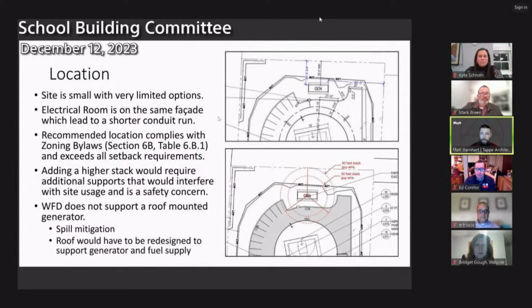We worked with our acoustical consultant to make sure that the control of noise to the neighboring properties was met for the DEP requirements. This location was also chosen due to its proximity to the electrical room, which is on the same facade. We looked at other options around the building as well, but moving it to the other side of the building led to a much longer conduit run, and we also did not want the conduit runs going underneath the building. The recommended location complies with all the zoning bylaws, section 6B, table 6B.1, and exceeds all the setback requirements.